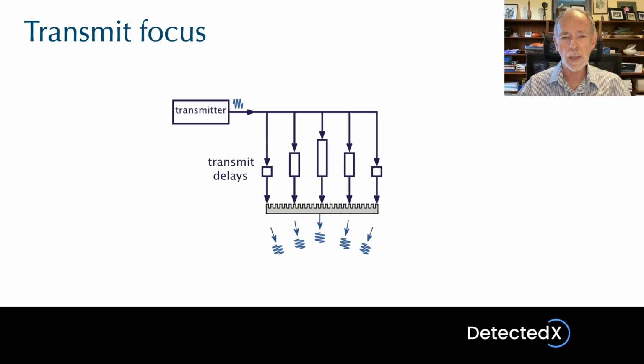So the transmit pulse is delayed by the largest amount before it reaches the central element, because that element is closest to the focal point. If we go to the outside edges of the transducer, you can see that the delay elements are the shortest of any of them, because we want these elements to transmit first, because the path distance from them to the focal point is going to be the longest distance.